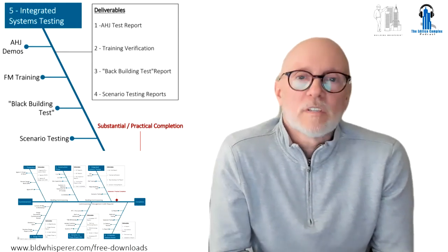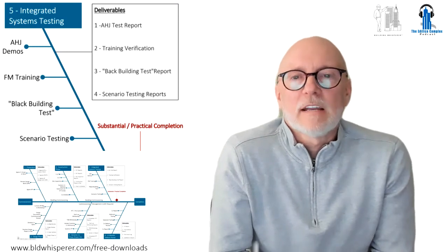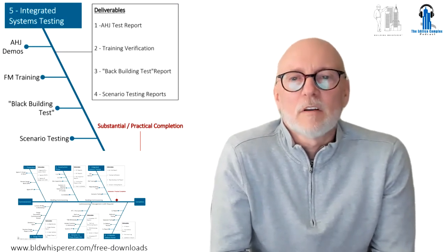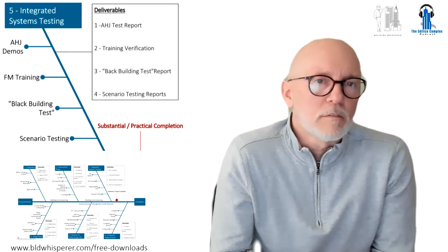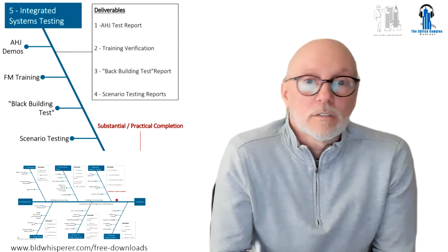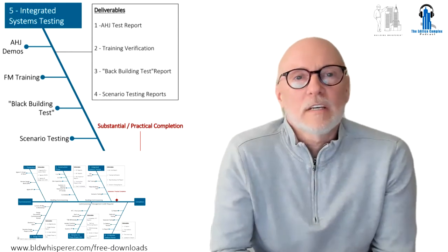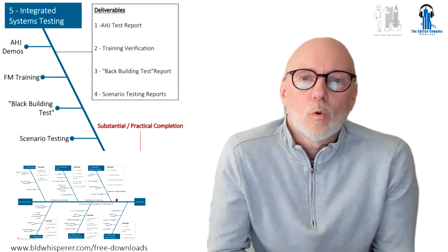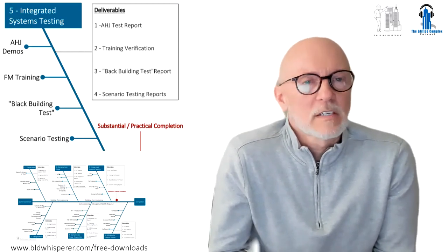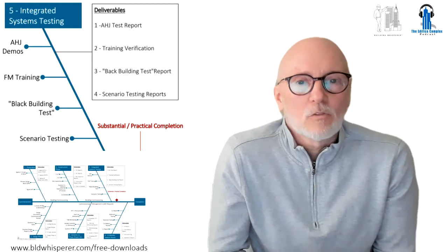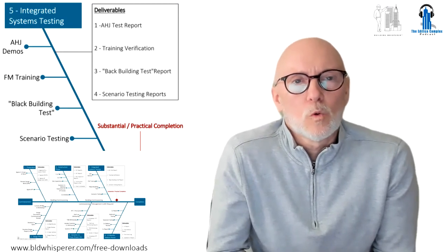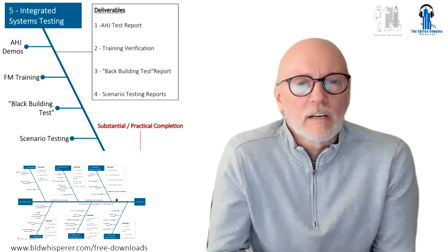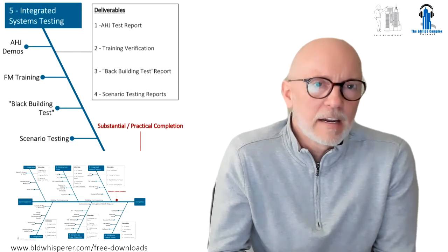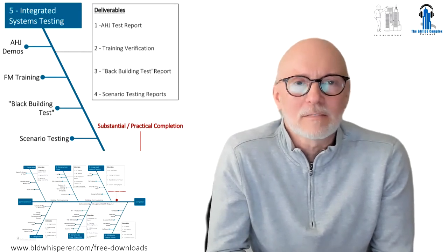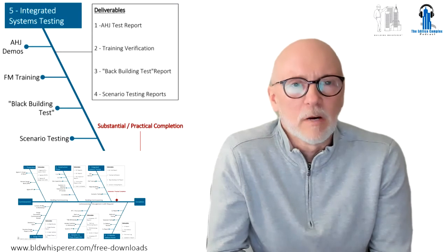Ironically, considering how important this is, there are no generally agreed standards. The best guidance out there at the moment is NFPA 3 and 4. Shout out to NFPA - in 2015 they issued a handbook called the Commissioning and Integrated Systems Testing Handbook. It is great, it really incorporates all the guidance and practice for NFPA 3 and 4 plus some extra guidance. It is, in my opinion, the gold standard out there at the moment.